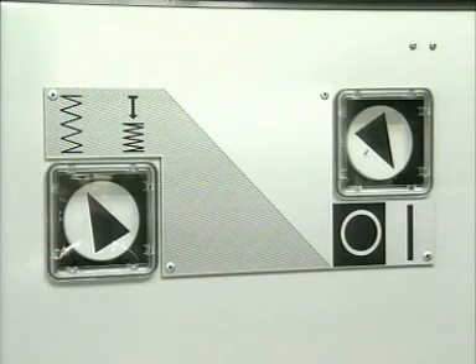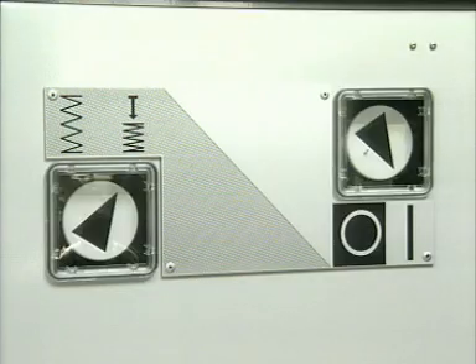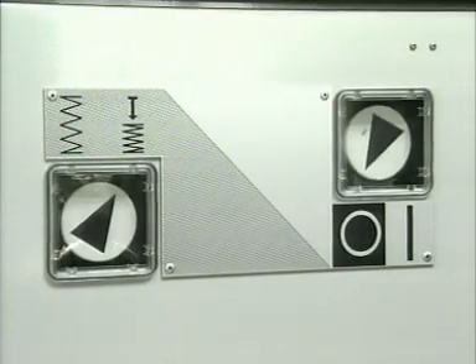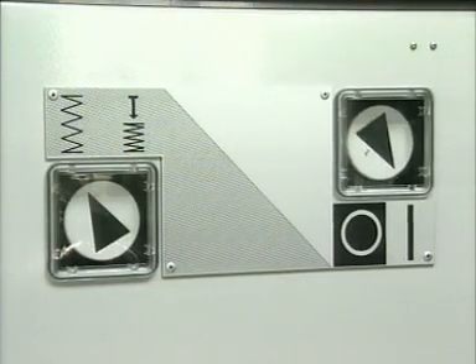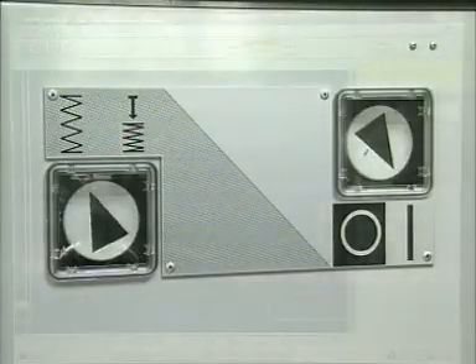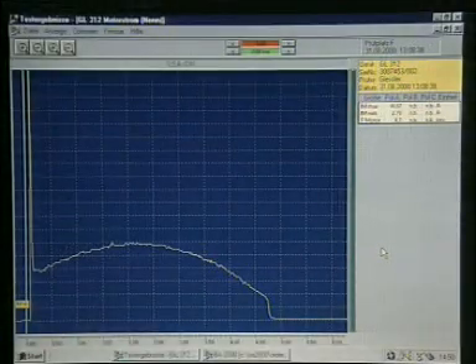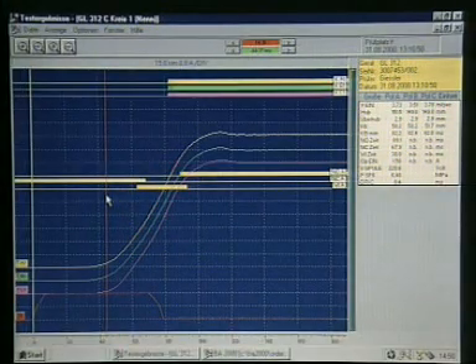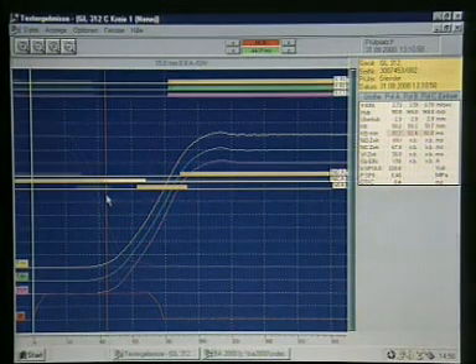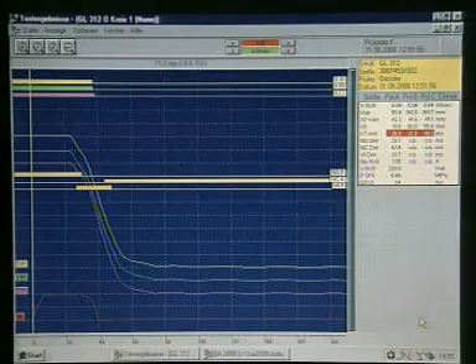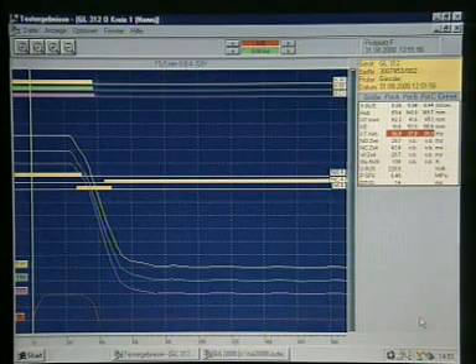Following the safety instructions in the operating manual, carry out 5 test operations, each in closed and open position by remote control. Then measure the motor running time after a closing operation. Measure the breaker operating times for 1 closing operation and 1 opening operation and plot the movement curves. Check the results against the routine test certificate and enter them in the checklist.